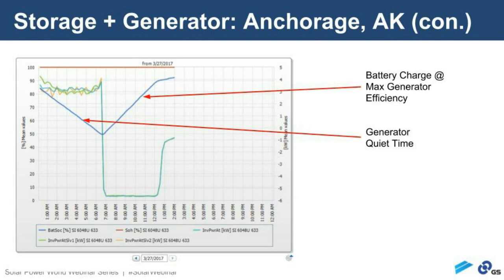Then this, starting from the left, is in the middle of the night when the lodge is basically asleep. Starting at 7 a.m., the inverters drop offline because the battery has reached, in this case, we had it set for 50% depth of discharge. This is when we first turned it on. We eventually moved it to closer to 70% depth of discharge. But the battery reached its maximum discharge point.